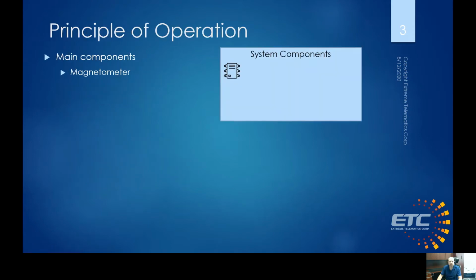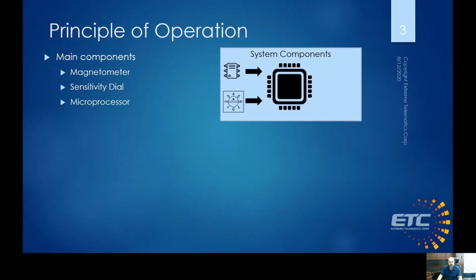So in terms of the principle of operation, the main system components on the circuit board in all of our sensors starts with a magnetometer, or a magnetic field sensor, that reads the Earth's magnetic field. We also have a sensitivity dial, which can be set from 0 to 7. These are both connected into a microprocessor that analyzes the data coming from the magnetometer and compares the signal to the switch setting to determine when to close the switch. It's a digital switch, and so what we can do is decide to hold it longer or decide when to and when not to close it.